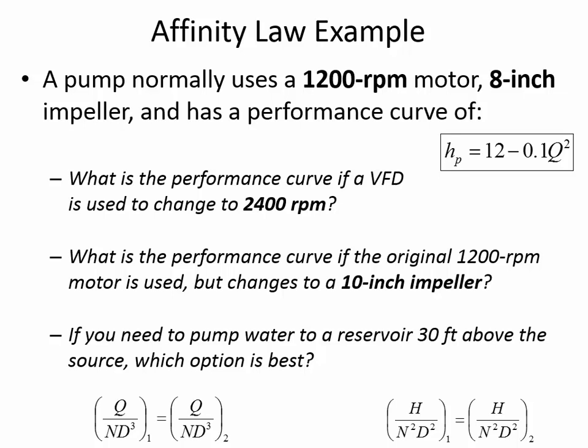0.25 H sub P2 is put in place of H sub P1, equals 12 minus 0.1 times 0.5 Q2 squared. So what that gives us is HP2 is 48 minus 0.1 Q2 squared. So this is the pump curve at 2400 RPM. So by spinning the pump twice as fast, we've quadrupled the cutoff head for this. All right, so that's if it's 2400 RPM.